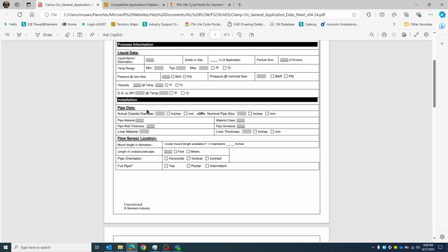Pipe data is also critical, and the reason for this is that we need to know what the outside diameter and pipe material is so we can come up along with wall thickness so that we can come up with the appropriate sensors for the application. If you know that there's a liner, please add that information along with the liner thickness.